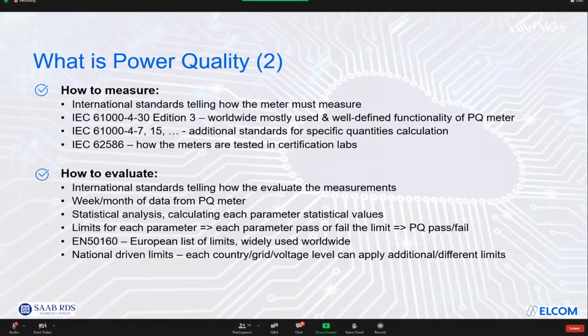There are international standards telling how these numbers from the power quality meter are evaluated. So at first you have raw data or calculated numbers from the PQ meter, and then you do statistical analysis, checking for each parameter, for example if the voltage is plus minus 230 volts, and statistical evaluation for the whole week, pass or fail. This is done for each parameter, so at the end you know if each one passed or failed. Overall, all parameters must pass for the power quality to pass overall.